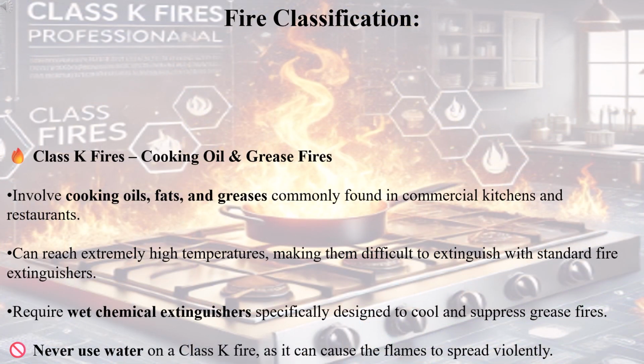Class K fires, cooking oil and grease fires, involve cooking oils, fats, and greases commonly found in commercial kitchens and restaurants. They can reach extremely high temperatures, making them difficult to extinguish with standard fire extinguishers. Require wet chemical extinguishers specifically designed to cool and suppress grease fires. Never use water on a Class K fire, as it can cause the flames to spread violently.